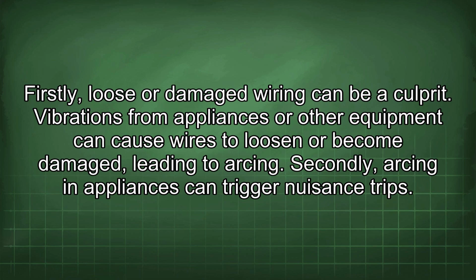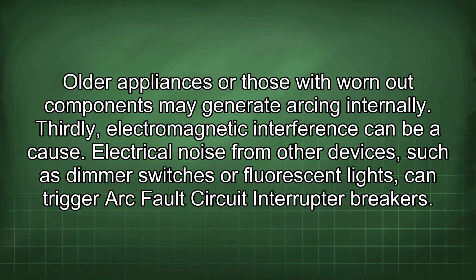Firstly, loose or damaged wiring can be a culprit. Vibrations from appliances or other equipment can cause wires to loosen or become damaged, leading to arcing. Secondly, arcing in appliances can trigger nuisance trips. Older appliances or those with worn-out components may generate arcing internally. Thirdly, electromagnetic interference can be a cause. Electrical noise from other devices, such as dimmer switches or fluorescent lights, can trigger arc fault circuit interrupter breakers.